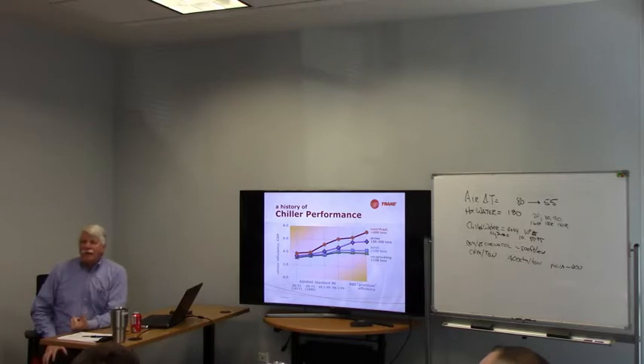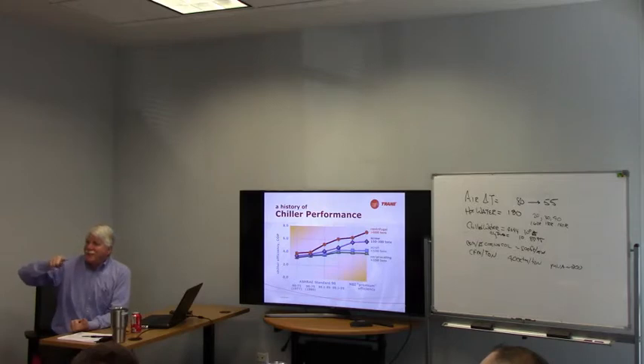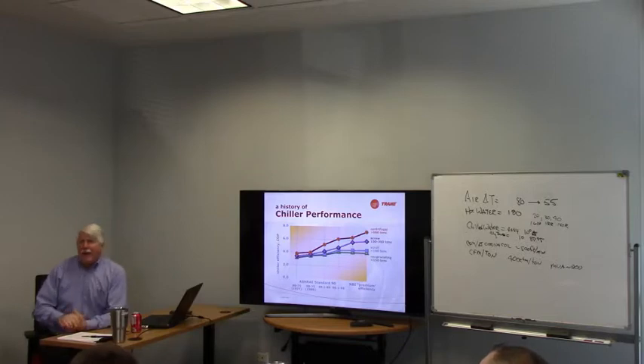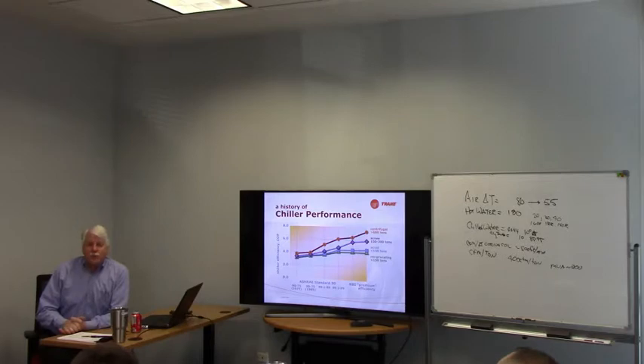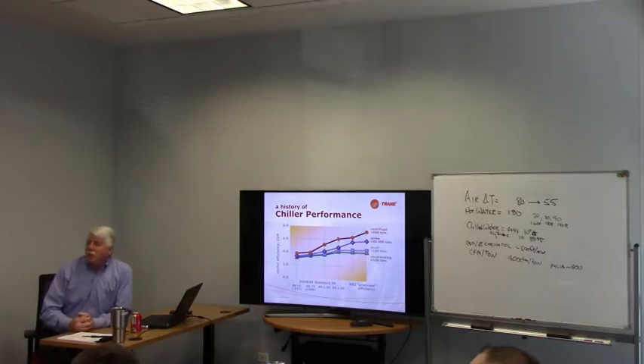And there is a theoretical limit of how much heat transfer you can put through there. Then somebody got the brainy idea of, if we put rifling inside the tube, it'll increase its heat transfer. And if we put fins on the outside of the tube, it will increase heat transfer. And that drove about 75% of the energy savings, was putting more tubes and more efficient tubes in chillers, okay? Now, if all it is putting tubes in chillers that makes them efficient, why don't we make them all really efficient?